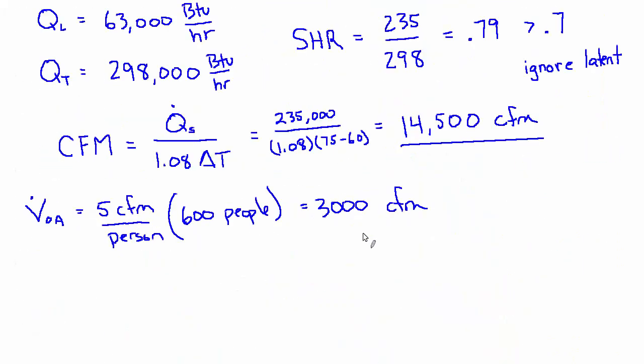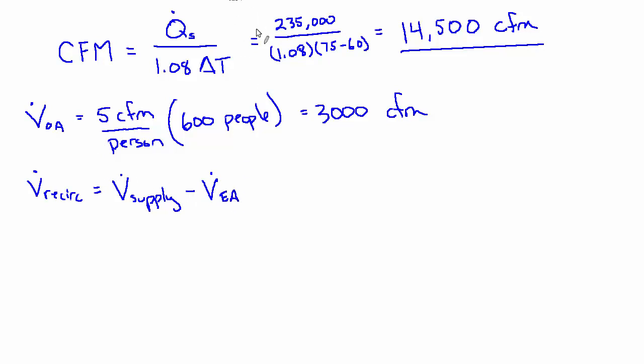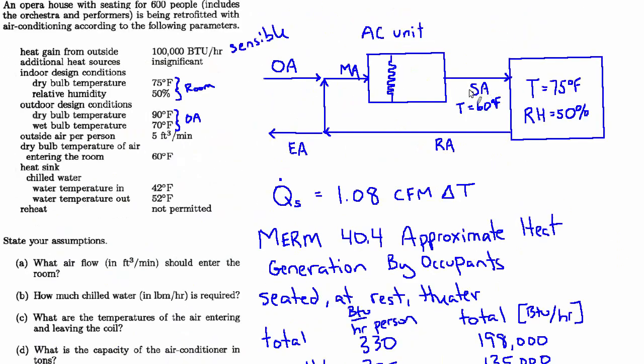So that's going to be 11,500, but let's write it out. So the volume of the recirc is the total volume of supply minus the volume of the exhaust air. And these are not special formulas that you need to worry about memorizing.